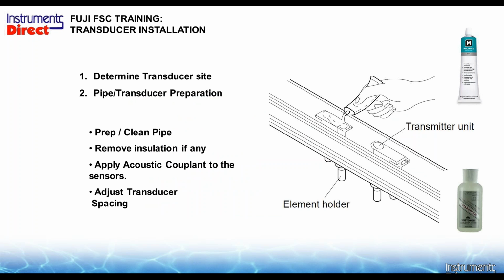Now we're going to get the transducer ready to put on the pipe. So we clean the pipe off, and what's required here is, if it has some insulation, we remove a piece of insulation. We don't cut little holes or a little strip to put the transducer on it. We take off a whole section of insulation so we can strap it on the pipe there. And as far as prepping the pipe, a rag will do, and if you've got some loose rust, maybe a wire brush, but we don't use a grinder. We don't need any paint thinner to take the paint off or anything like that. If it ain't moving, leave it there.